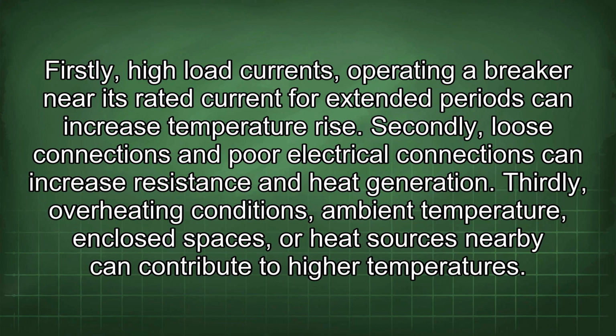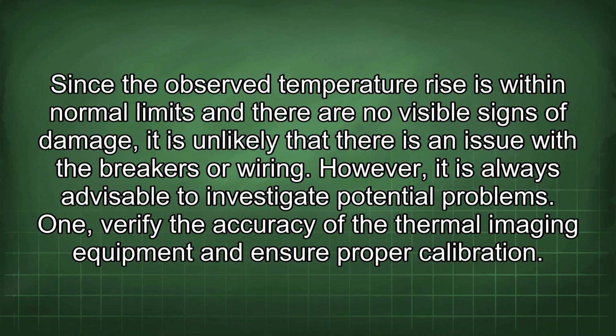Firstly, high load currents operating a breaker near its rated current for extended periods can increase temperature rise. Secondly, loose connections and poor electrical connections can increase resistance and heat generation. Thirdly, overheating conditions, ambient temperature, enclosed spaces, or heat sources nearby can contribute to higher temperatures. Since the observed temperature rise is within normal limits and there are no visible signs of damage, it is unlikely that there is an issue with the breakers or wiring. However, it is always advisable to investigate potential problems.